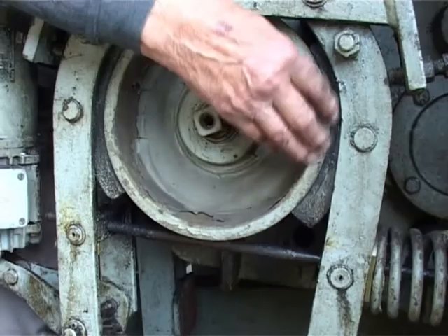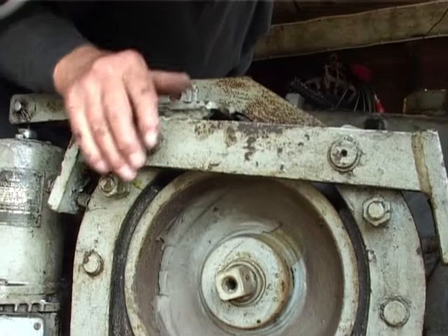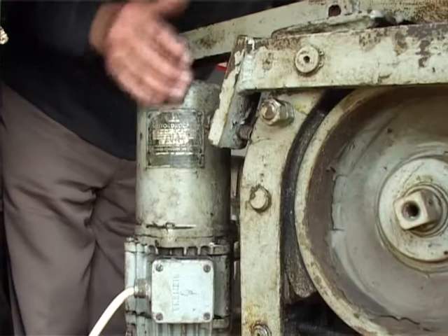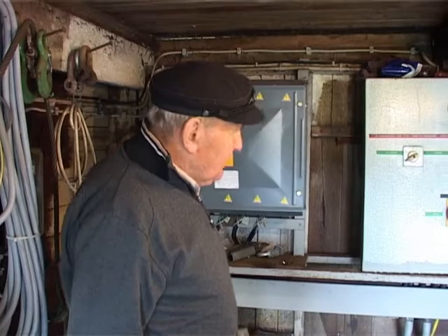This is the brake. And these are the two bolts which are holding the brake. And what is that cylinder? This is the automatic motor brake driver, which always keeps the brake engaged when there is no electricity. When it receives electricity, it releases and makes the brake loose. This is how the motor driver works.